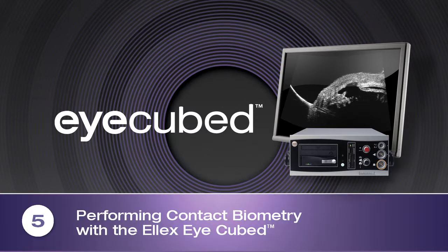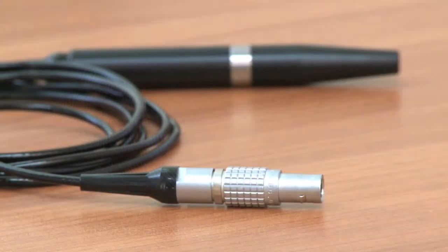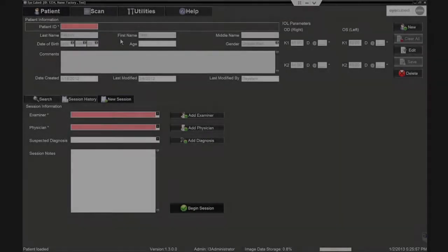Performing contact biometry with the Ellex Eye Cubed. Performing contact biometry with the Ellex Eye Cubed is easy, fast, and accurate. Ensure that the 10 MHz biometry A-scan probe is connected to the Eye Cubed console and turn on the system. The patient screen is displayed.